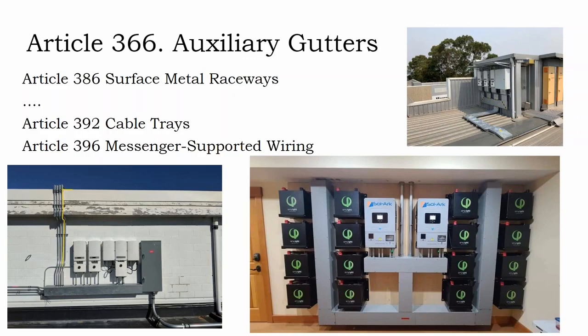So we redid it to make it look better, and admittedly, it does look better, but also admittedly, cable tray should have been specified instead, because by the time you evaluate all of that work, you're spending as much on labor instead of getting a higher quality finish.